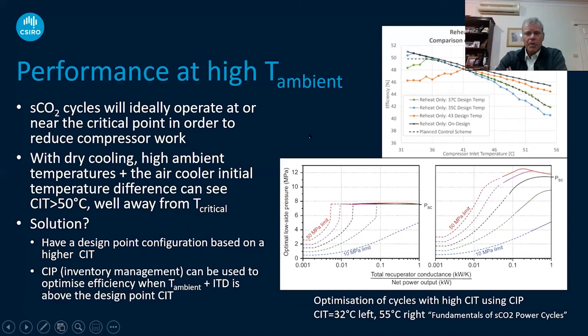Again, on this issue of higher ambient temperatures: you want the supercritical CO2 cycles to ideally operate near the critical point in order to reduce that compressor work. Now with dry cooling, you've got high ambient temperatures as well, and if you add that high ambient temperature to the air cooler initial temperature, you're going to get a compressor inlet temperature 50 degrees C or above, which again, as I said before, is well away from the critical temperature.